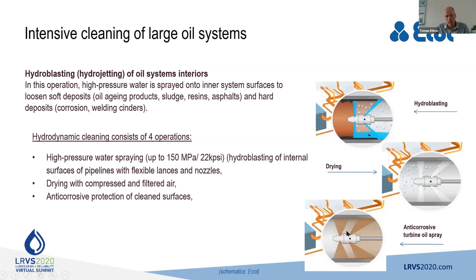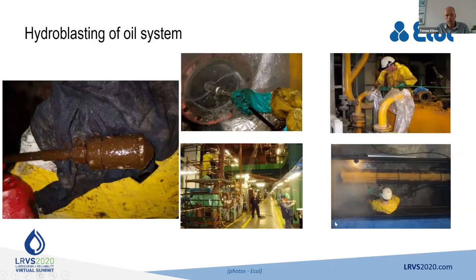At the end of that process, all the open points, flanges are covered with caps or with some specific foil against secondary contamination. So in that process, pipes one by one, all the branches, all the main lines are cleaned with high pressure water, and also the components. You can see that on some pictures I put here. So we take care, of course, of the waste visible on that. Components that are disassembled to let us enter the pipes with the high pressure nozzle are cleaned in a special tank, and the components like oil coolers and some pipe segments are cleaned here as well.